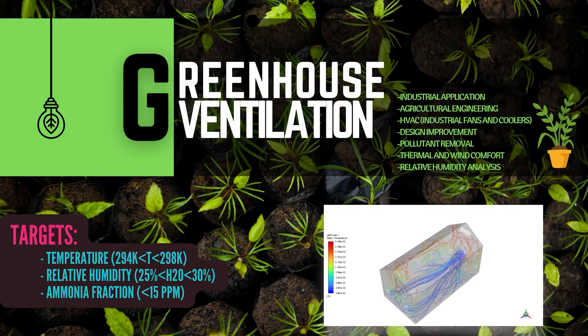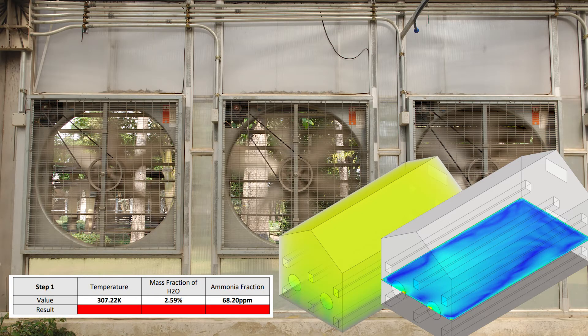In the first step, the greenhouse is simulated with its initial condition considering two industrial vents. After the simulation, the results analysis shows that the volume average temperature, the relative humidity, and ammonia concentration reveal the greenhouse's critical condition. Also, the extracted temperature and velocity contours show the inefficient ventilation system that didn't have the ability to recirculate air effectively, and the bulk air remains stagnant except around the fan region. So, this couldn't satisfy either of the criteria.